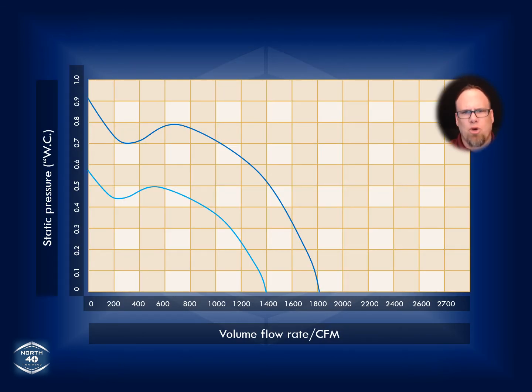So looking at a blower performance chart, this is another version of the blower performance chart in which you see what's called a fan curve. Those two weird lines in all the checkers there are telling you where that fan is operating as far as CFM goes and static goes throughout the cycle of that fan operating. Okay, so if you look across the bottom, you see the CFMs. Okay, that is airflow and CFMs.